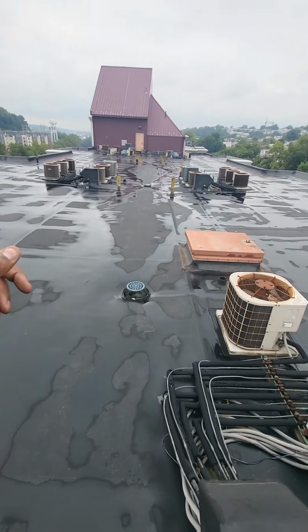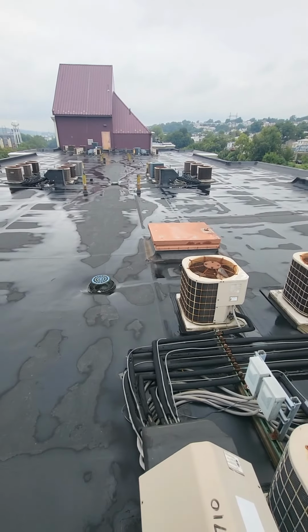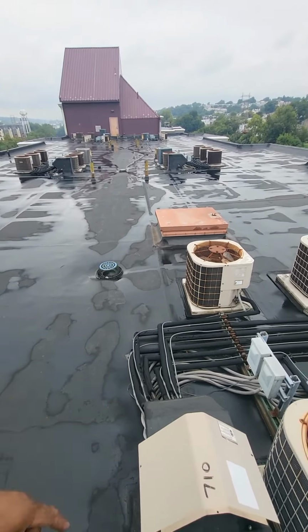So how I got to that conclusion, guys, is I removed the thermostat wires from the board, and by me removing the wires from the board, that pretty much eliminated my contactor and my low voltage wires to my condenser and my low voltage wires to my thermostat. So the only thing that could be left on the low voltage circuit inside is the board if you remove all the wires.